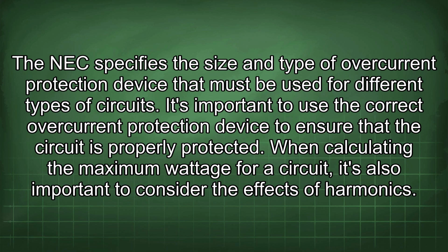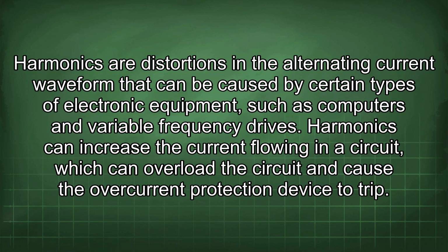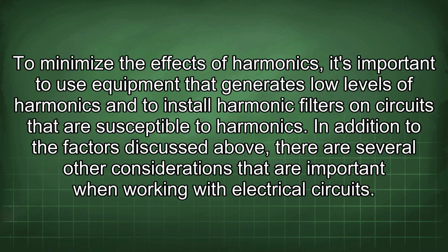When calculating the maximum wattage for a circuit, it's also important to consider the effects of harmonics. Harmonics are distortions in the alternating current waveform that can be caused by certain types of electronic equipment, such as computers and variable frequency drives. Harmonics can increase the current flowing in a circuit, which can overload the circuit and cause the overcurrent protection device to trip. To minimize the effects of harmonics, it's important to use equipment that generates low levels of harmonics and to install harmonic filters on circuits that are susceptible to harmonics.